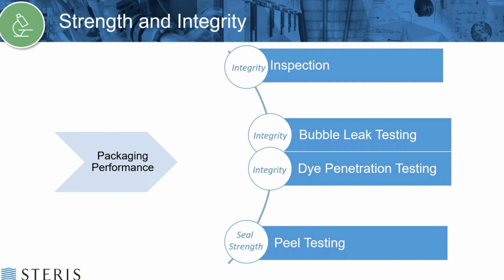Some other integrity tests include a bubble leak test, where you submerge the package underwater and inflate it with air and observe for steady streams of bubbles indicating a channel through a seal, or perhaps a pinhole, or any sort of breach in your sterile barrier. There's also dye penetration testing as an integrity test. This is where you would inject a purple dye into the pouch or the package and observe for that dye leaking through, again indicating a channel through a seal or some sort of breach in that sterile barrier integrity. The most common seal strength test that we see is a peel test. This is where you're going to cut a segment of each side of the package and pull those two sides of the package apart, measuring the amount of force required to do so.